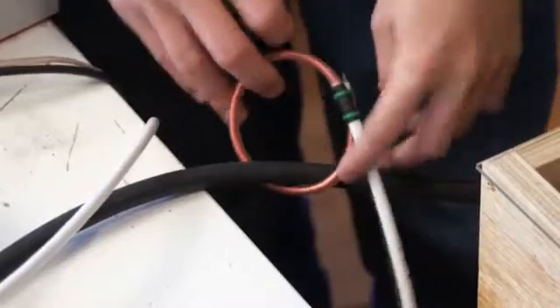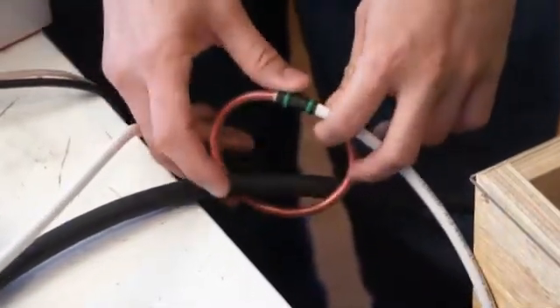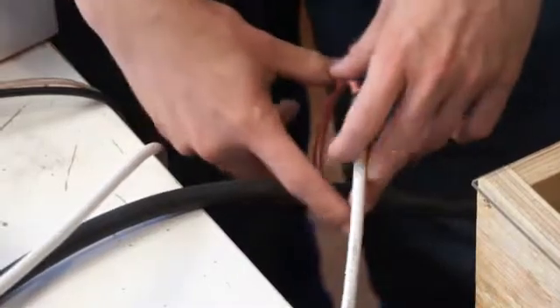Now this current sensor is actually something called a Rogowski coil, it's a flexible current sensor that you can wrap around conductors which are already installed.